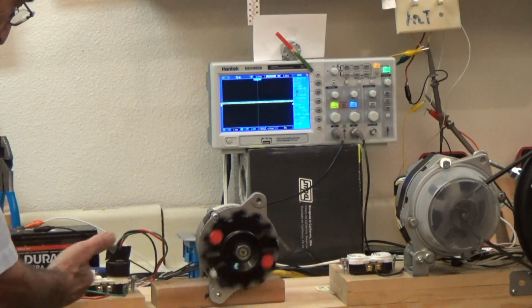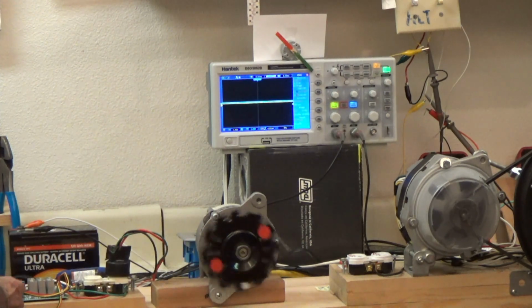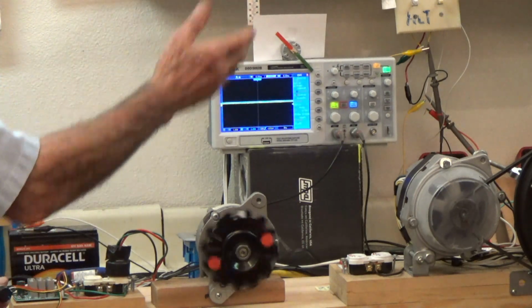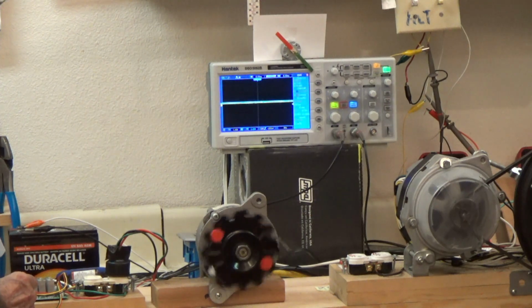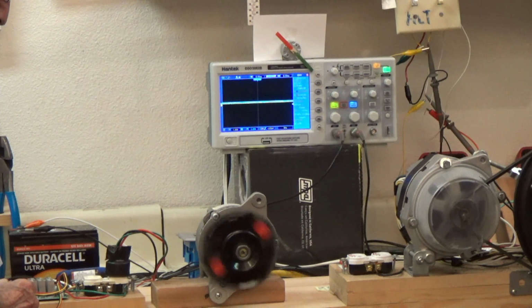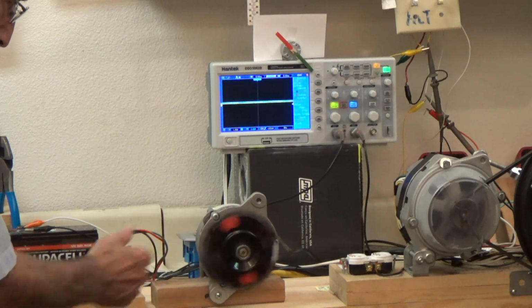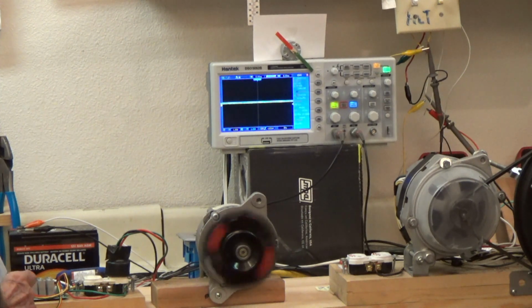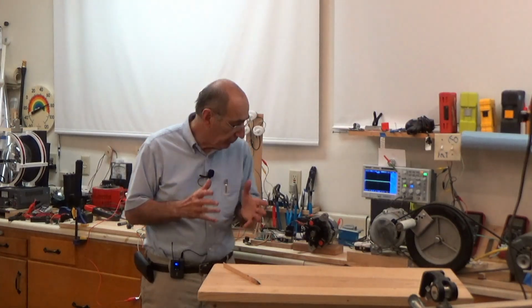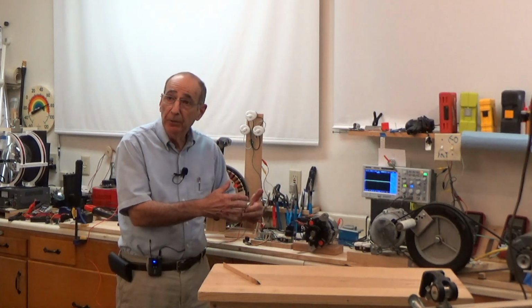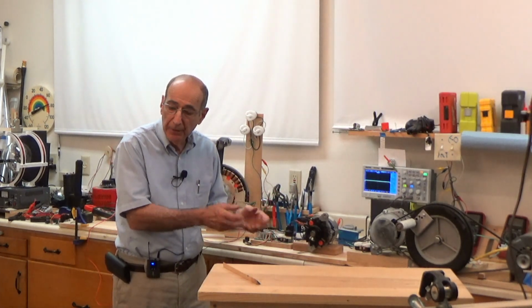And now it knows exactly what speed it's going at, and if I want a higher speed, it won't just increase the frequency, it will sense what it's doing, how fast it's going, and carefully increase the frequency as the motor can handle it until it gets to what I've set it for. So the trick is to sense what the motor is doing and give it electricity it can really use.